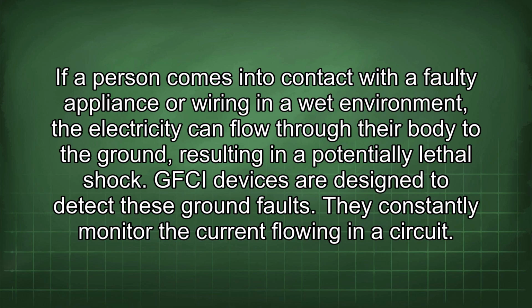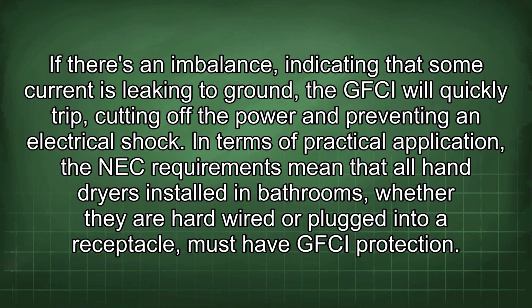GFCI devices are designed to detect these ground faults. They constantly monitor the current flowing in the circuit. If there's an imbalance, indicating that some current is leaking to ground, the GFCI will quickly trip, cutting off the power and preventing an electrical shock. In terms of practical application, the NEC requirements mean that all hand dryers installed in bathrooms, whether they are hardwired or plugged into a receptacle, must have GFCI protection.